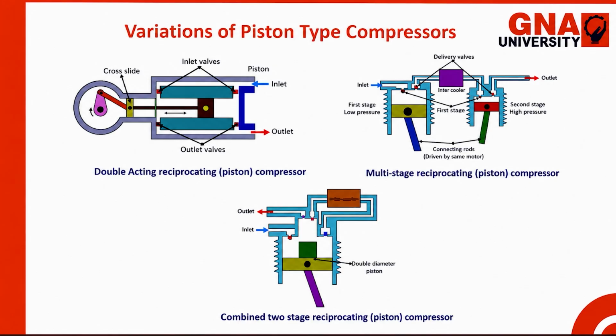In this, there are two stages, but you achieve those two stages using only a single piston and cylinder arrangement, with a very little modification in the construction of the piston. So what happens when the inlet air comes here? You see that the air gets entrapped in these areas. Now it gets compressed, and the compressed air moves through this annular passage to the intercooler.